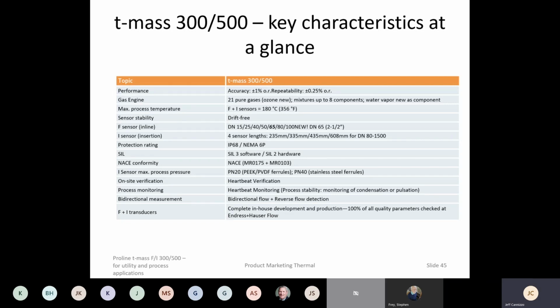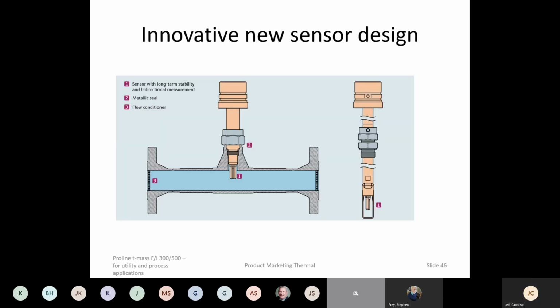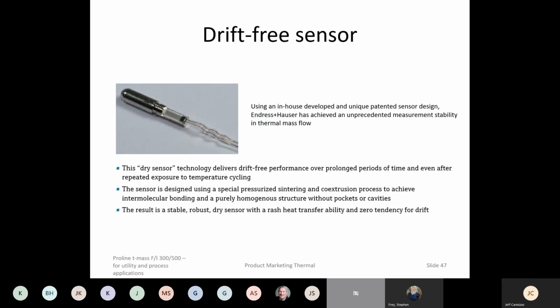IP68 NEMA 6P conforms to NACE if needed. We offer the heartbeat verification, which we haven't talked too much about, but is a program that resides within the meter that allows you to test the meter internally to make sure it's still operating within the specifications it was when it left the factory. We can do bi-directional flow with this meter. So that's the sensor design. If you buy the inline version, flow conditioners are built in. The sensor's removable, so if you need to send it back for calibration, you can leave the body in line and just send back the sensor. It's some nice features. And there's the drift-free sensor.